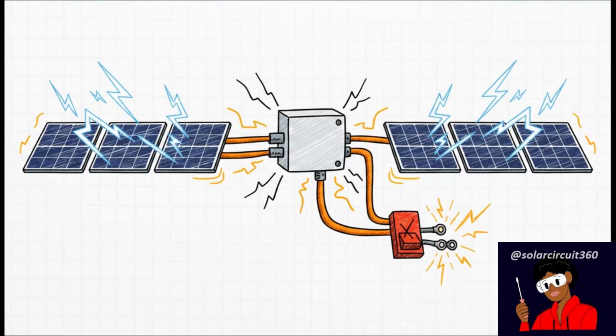Now, what's really interesting about this is how the physical consequences of that lag compound. This is the climax of what we're talking about today. Here are 5 physical risk points that occur when current spikes and voltage drifts simultaneously. First, the controller's max input voltage limit is pushed to the absolute brink, especially in those cold conditions with returning bright sun we talked about.